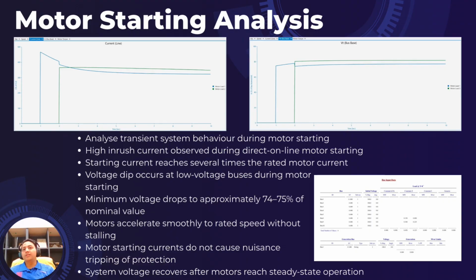Even though the voltage drops, both motors are still able to speed up smoothly and reach their normal operating speed without any problem. After the motors finish starting, the current reduces and the voltage slowly returns to its normal level. The results also showed that the protection devices do not trip during motor starting, which means the system is able to handle motor starting safely.